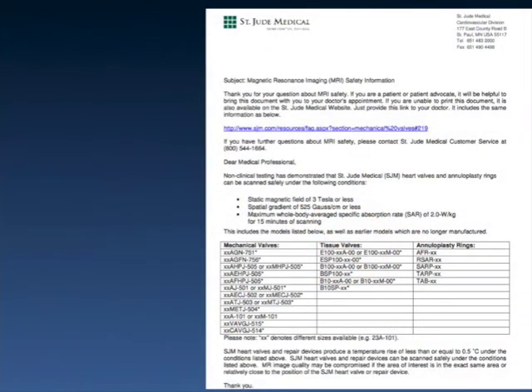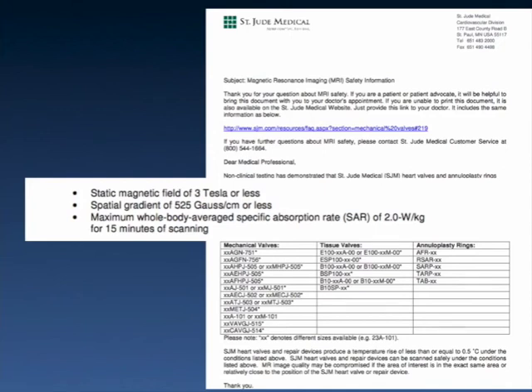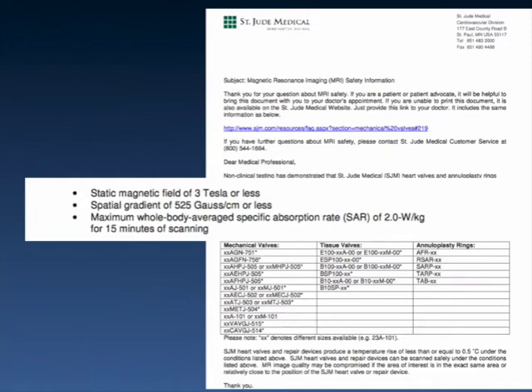Here's an example — a letter obtained from a client who requested MR labeling information from St. Jude about a particular heart valve. As you can see, the conditions of use are: static magnetic field of three Tesla or less, spatial gradient of 525 Gauss per centimeter or less, and maximum whole body averaged specific absorption rate (SAR) of 2.0 watts per kilogram for 15 minutes of scanning. This 15 minutes means per sequence — it doesn't mean you have to stop scanning after 15 minutes. It means you can't do any series that lasts more than 15 minutes, and most people have no problem adhering to that condition.